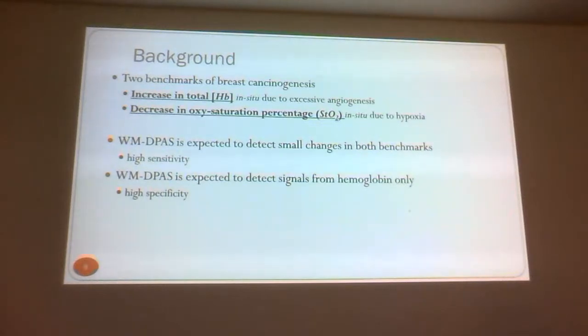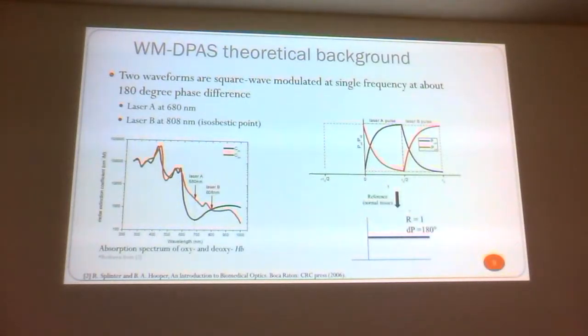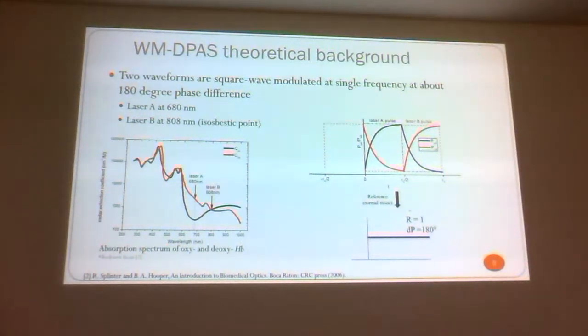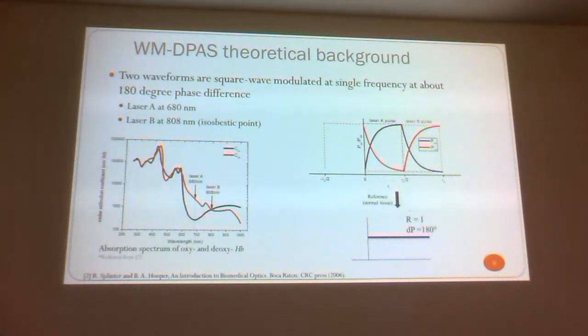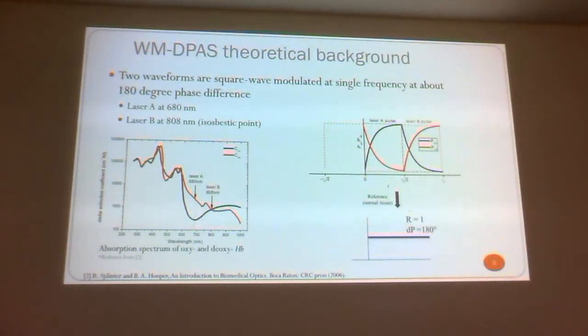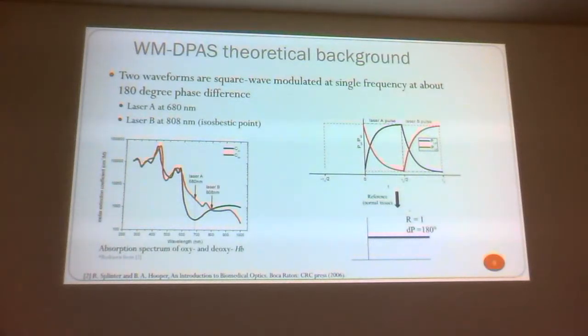This is the hemoglobin absorption spectrum. Because we have very high control of the frequencies — going back to the unique situation with frequency domain as opposed to pulsed laser — I can hone into two wavelengths. This wavelength is called the isosbestic point, where oxy-hemoglobin and deoxy-hemoglobin have the same absorption coefficient — that's good because it's a reference wavelength. Then I go to 680 nm, where there's a very high change in the absorption spectrum between deoxygenated and oxygenated. Deoxy is up here with the high absorption coefficient, and oxy is the low absorption coefficient.